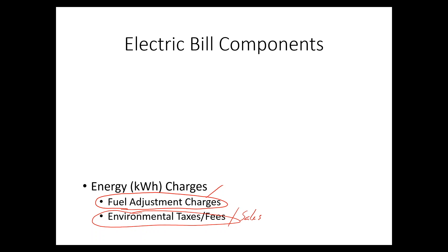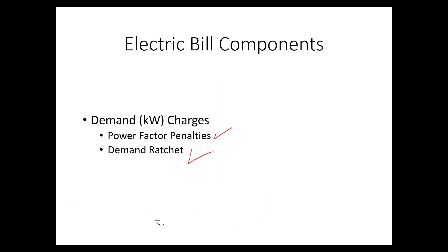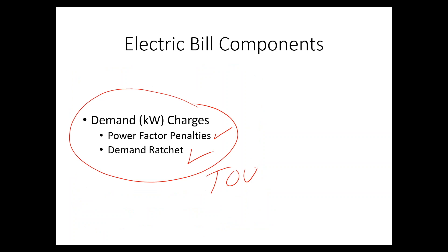All of these charges apply to every kilowatt-hour you use — the more kilowatt-hours, the higher the charges and fees. There's also another element to demand charges called time of use (TOU). If you use a lot of power in the afternoon when air conditioning loads are high, the utility is generally going to charge you more. This might be during summer afternoons, or all year during afternoons, depending on the utility and climate. Almost all utilities watch when you're using power, and if you use power during peak hours — say, 2 to 7 o'clock in the afternoon — they charge you more per kilowatt or kilowatt-hour during that period.